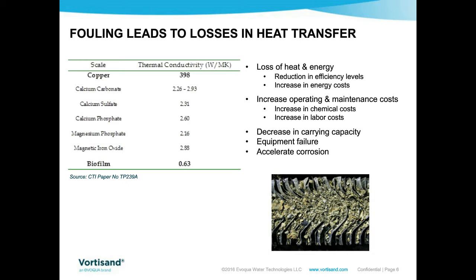countries. So it is important to know that in closed loops, for example, inorganic scaling and corrosion, or biofilm, and even organic components such as grease, wax, carbon, or polymers can significantly reduce the thermal conductivity of the heat exchangers. And that translates to more maintenance, increased differential pressure, so more energy requirement just to pump water through the heat exchanger, increase in chemical costs, biocides, corrosion inhibitors, acid and caustic cleaners, and downtime. And downtime leads to production losses.